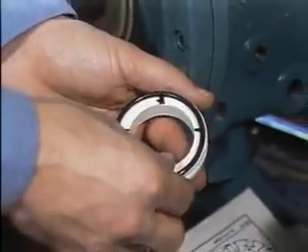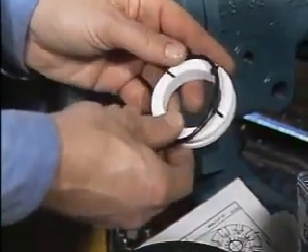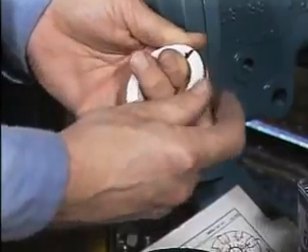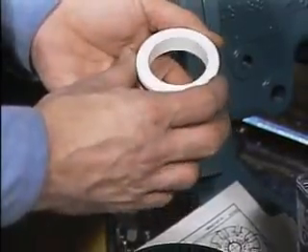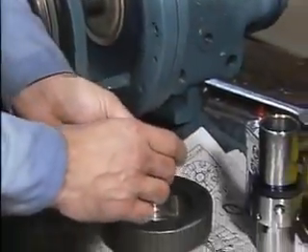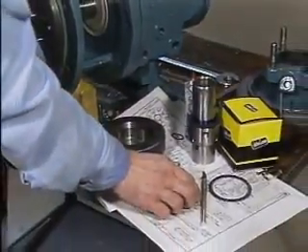However, some mechanical seal components can be damaged because they're relatively soft. For example, during installations, O-rings or bellows are sometimes cut by sharp edges on the shaft, such as shaft shoulders or shaft keyways. The causes of mechanical seal problems that we've just covered should give you an understanding of why seals fail. When a defective seal is replaced, it's often possible to examine the seal's parts to find clues for the source of a problem. For instance, it may be possible to identify causes of some seal problems by examining the wear patterns on seal faces.